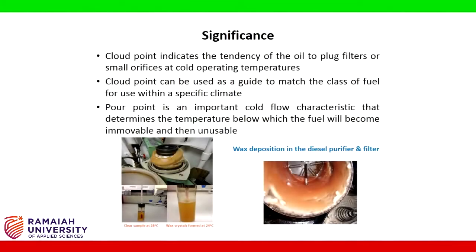What is the significance of cloud and pour points? Cloud point indicates the tendency of the oil to plug filters or small orifices at cold operating temperatures. Cloud point can be used as a guide to match the class of fuel for use within a specific climate.